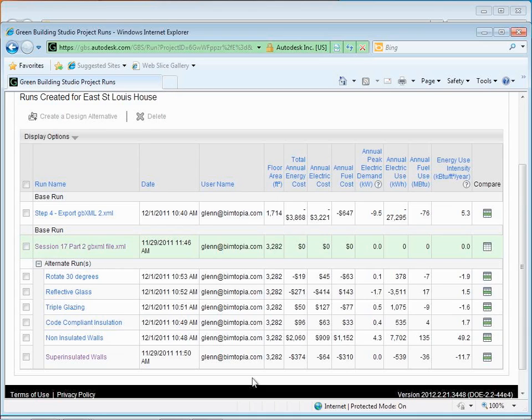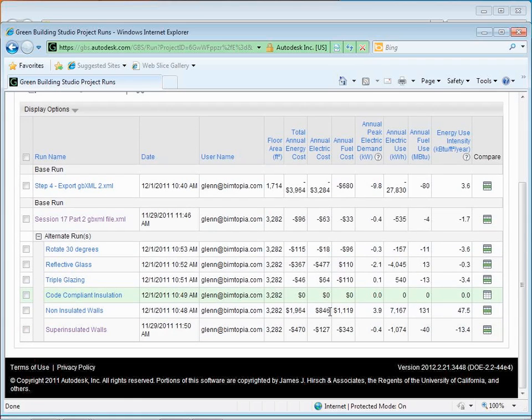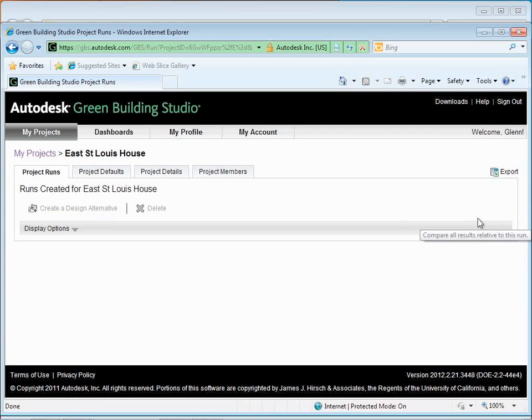What can we actually see? The non-insulated walls were a whole lot worse, about 50% worse than putting some insulation in there. So the insulation is definitely having some value. If I start looking at comparing to, say, code-compliant insulation, though, let me go to that one. Just the base for what's required for the code. You'll see that non-insulated walls are a lot worse. For super-insulated walls, 13 kilobtus per square foot per year better. So somewhat better, but it's not huge. You've got to start thinking about whether the cost of adding that insulation is worth the savings over the lifetime of the building and all the energy or carbon impacts it might have too.